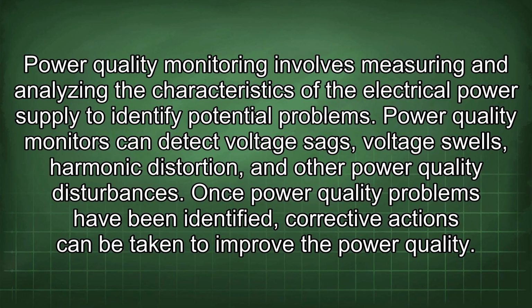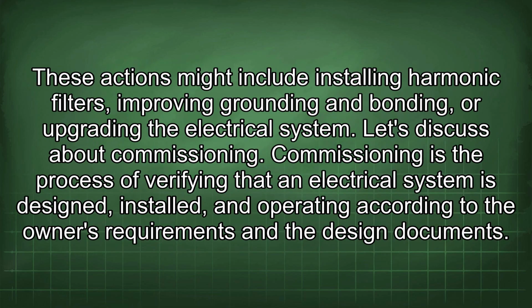Once power quality problems have been identified, corrective actions can be taken to improve the power quality. These actions might include installing harmonic filters, improving grounding and bonding, or upgrading the electrical system. Let's discuss commissioning. Commissioning is the process of verifying that an electrical system is designed, installed, and operating according to the owner's requirements and the design documents.